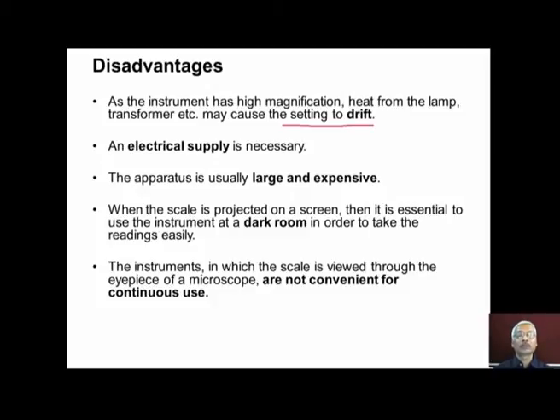When the scale is projected on a screen, it is essential to use the instrument in a dark room in order to take the readings easily. If there is too much light in the room where the optical comparators are placed, then taking readings becomes a bit difficult. The instruments in which the scale is viewed through the eyepiece of a microscope are not convenient for continuous use, since the operator is subjected to eye fatigue.